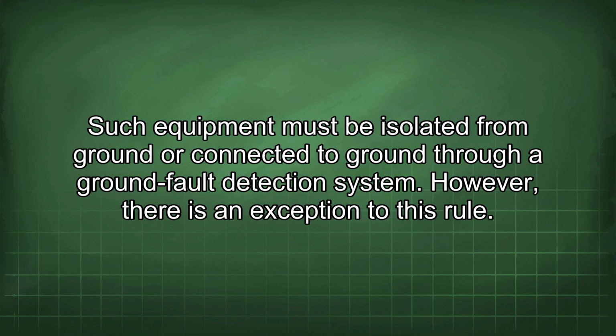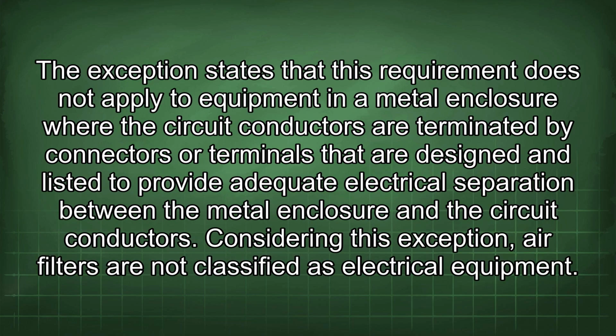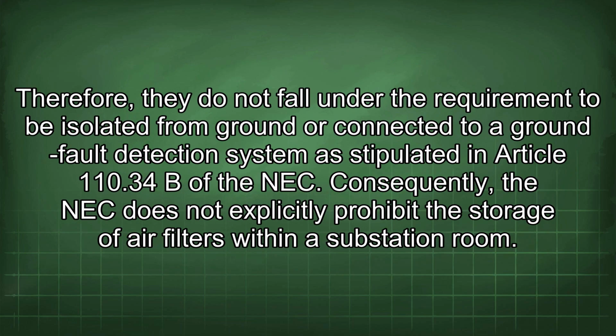However, there is an exception to this rule. The exception states that this requirement does not apply to equipment in a metal enclosure where the circuit conductors are terminated by connectors or terminals that are designed and listed to provide adequate electrical separation between the metal enclosure and the circuit conductors. Considering this exception, air filters are not classified as electrical equipment. Therefore, they do not fall under the requirement to be isolated from ground or connected to a ground fault detection system as stipulated in Article 110.34(B) of the NEC.